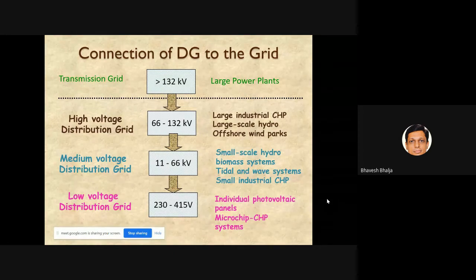You can also connect at 11 kV to 66 kV, the medium voltage distribution grid. In our case, we have distribution grid only up to 11 kV. Anything above that we treat as sub-transmission level, because above 11 kV we have 33 kV and 66 kV. But nowadays 33 kV is not there, the utility is removing it, so after 11 kV we immediately have 66 kV.